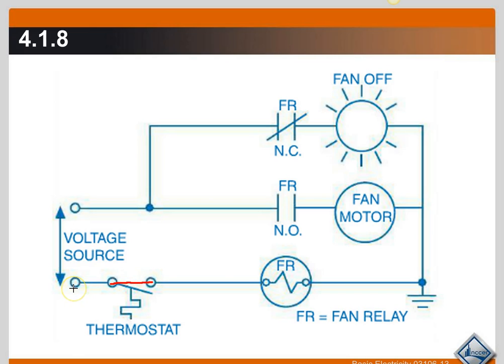So it closes this switch. It applies power to the fan relay coil which creates a magnetic field to switch the electrically controlled switch. When the thermostat closes and the fan relay coil gets power, the magnetic field is going to close the normally open contact and that's going to make it a closed contact.